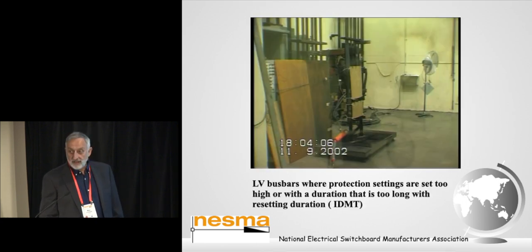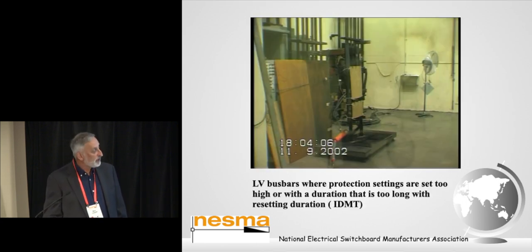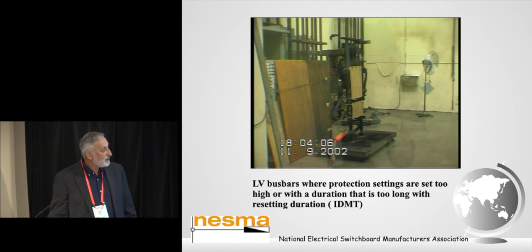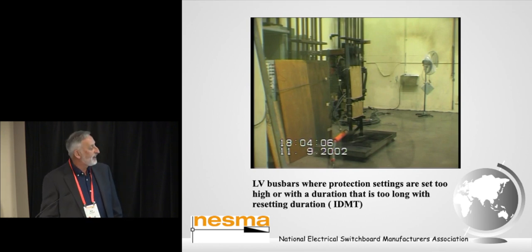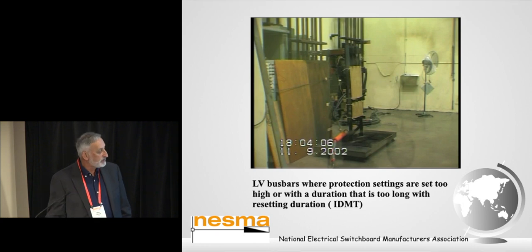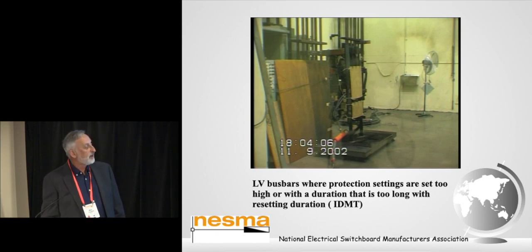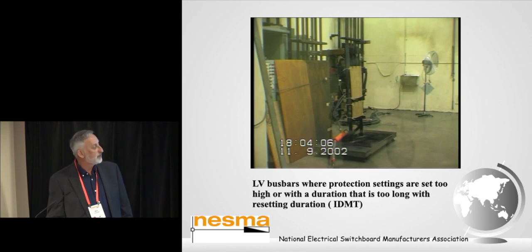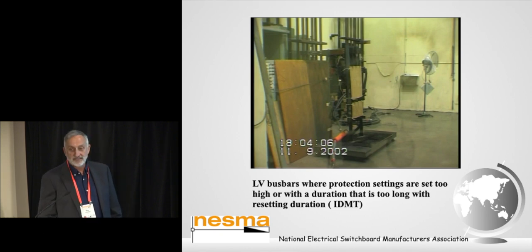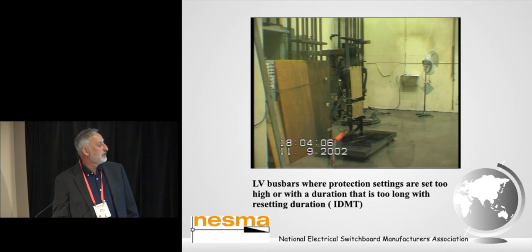So, as this is a very bland shot, I thought it was time to wake you all up. Here we have a series of 400 volt bus bars. There is a bit of plywood over the top, which was applied as screening to stop inadvertent touch contact with the bus bar itself. There's a steel rail on either side of the bus bar, with bus bar spacings just over 100 mil.